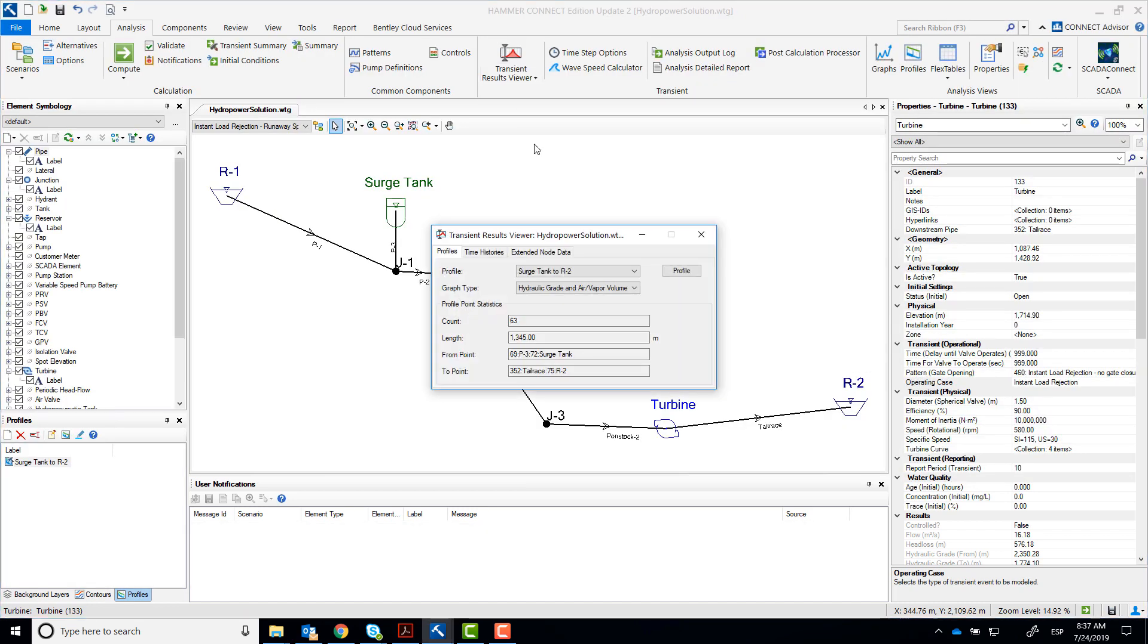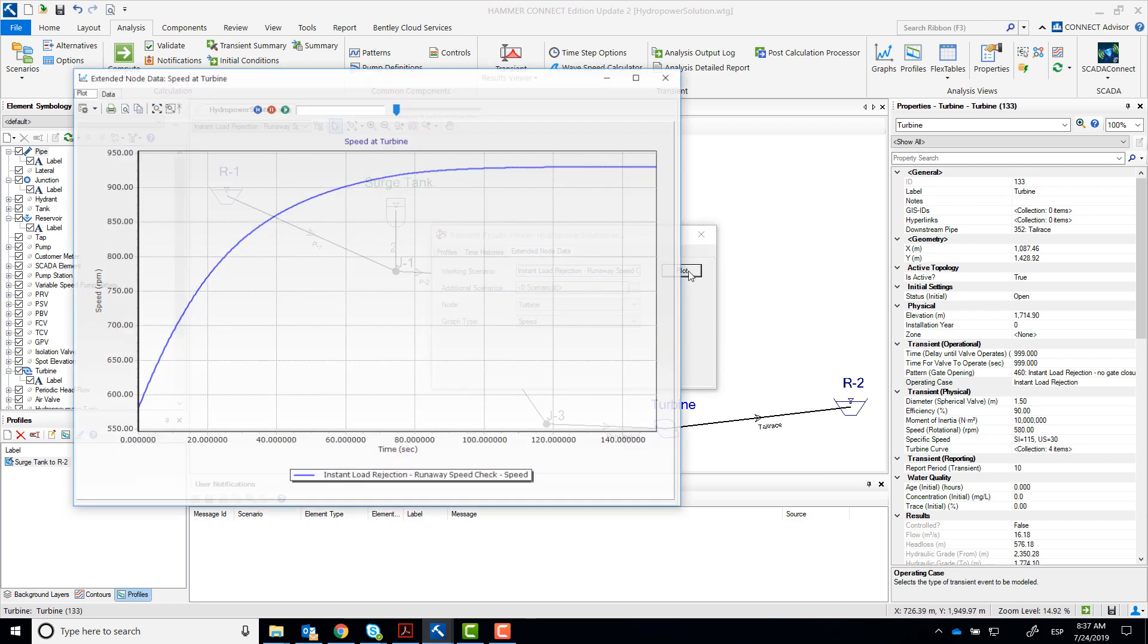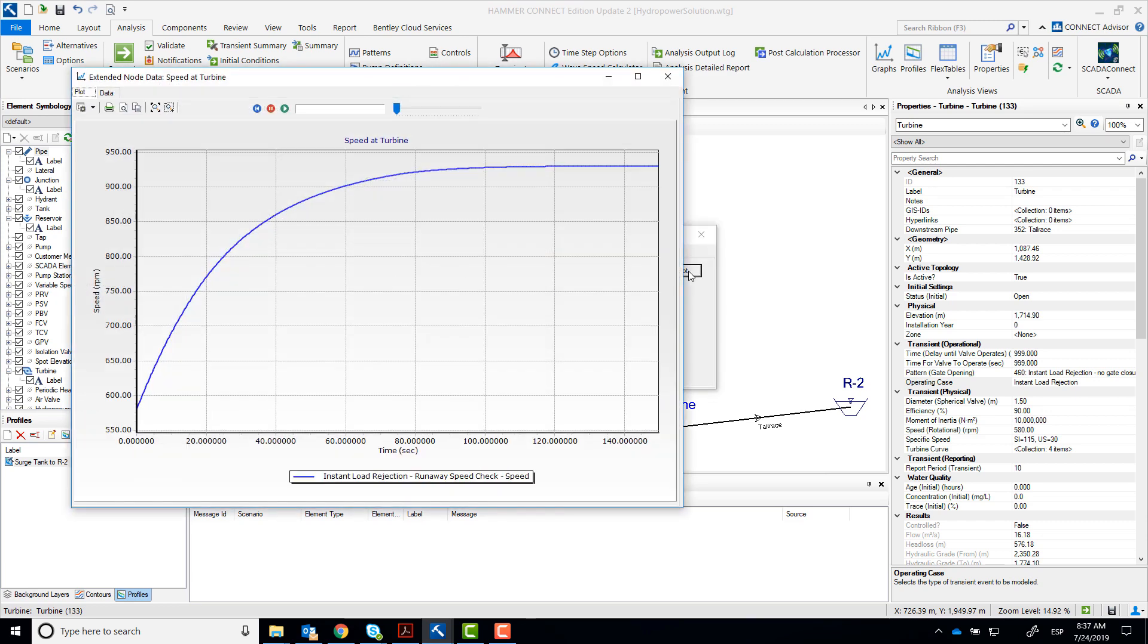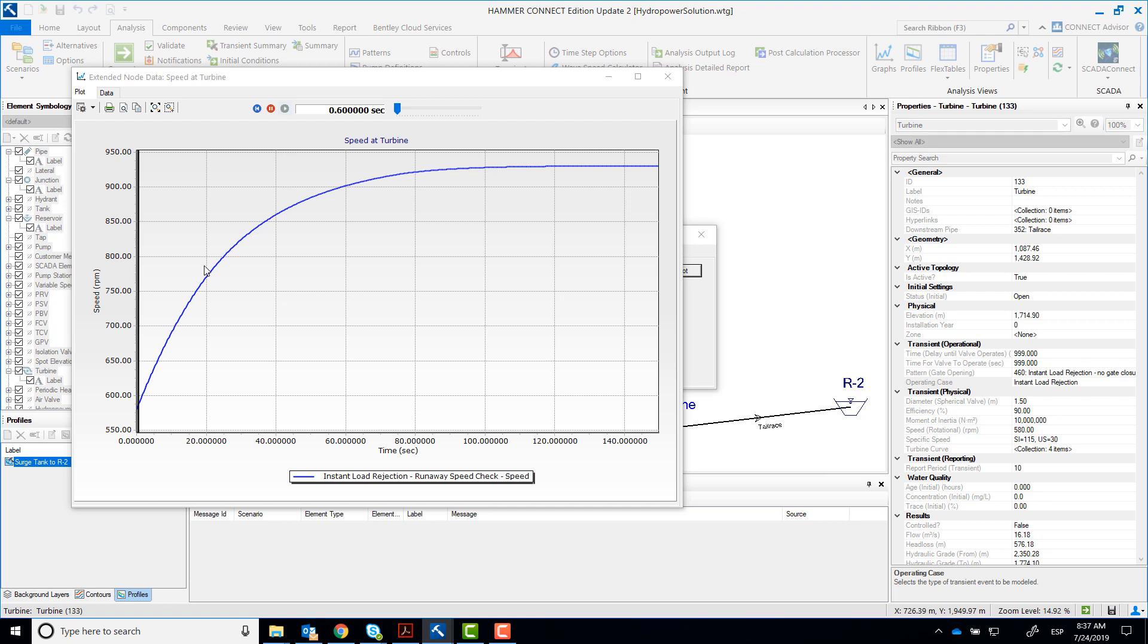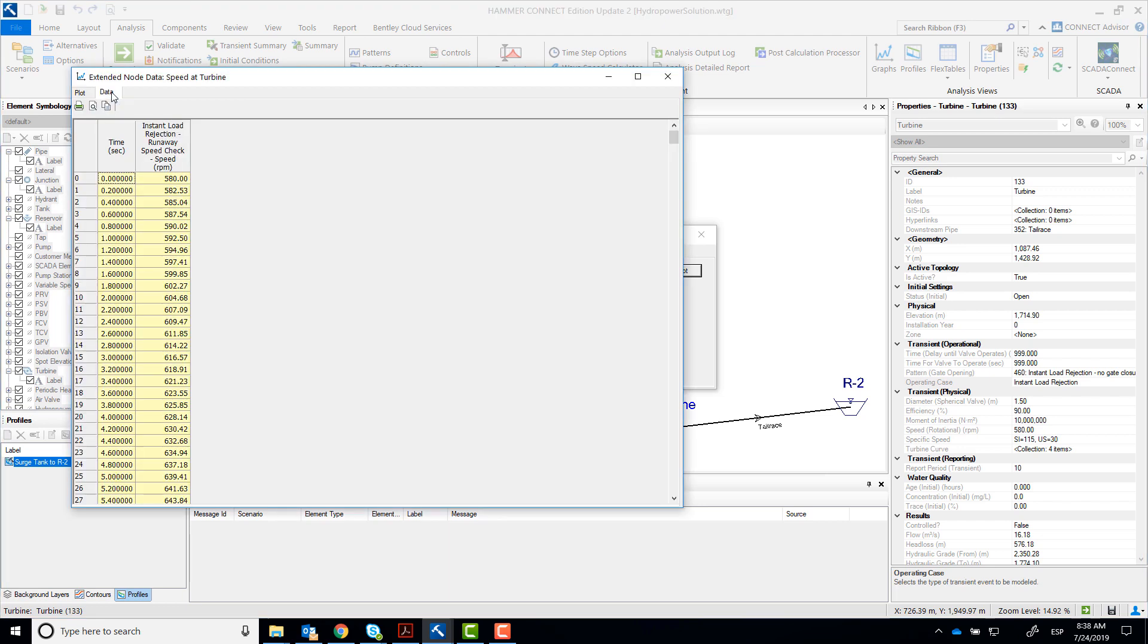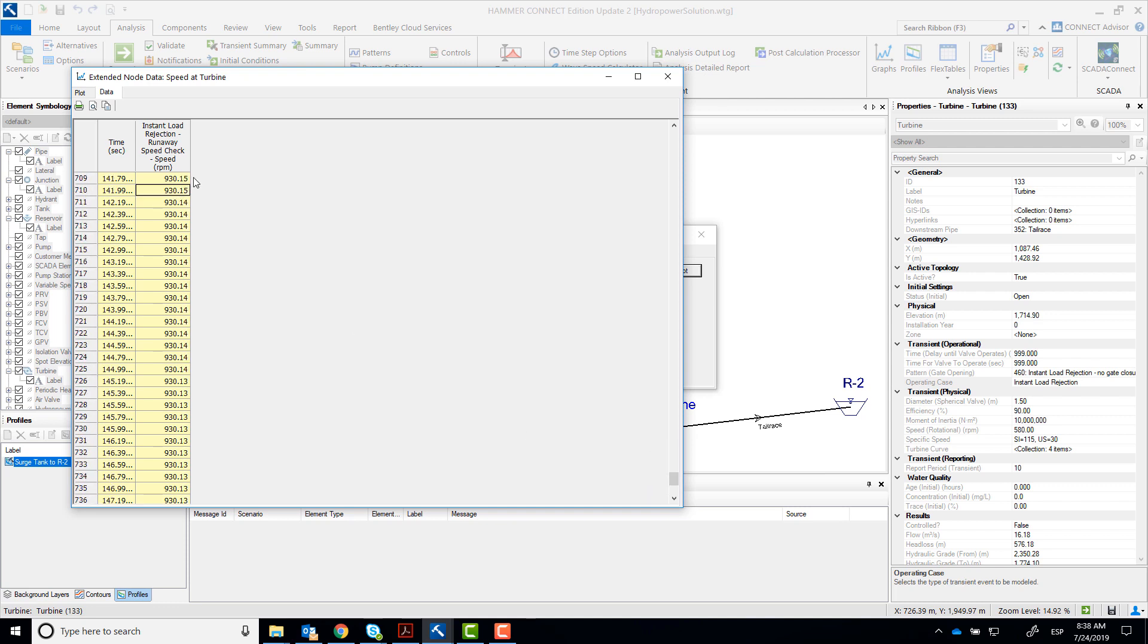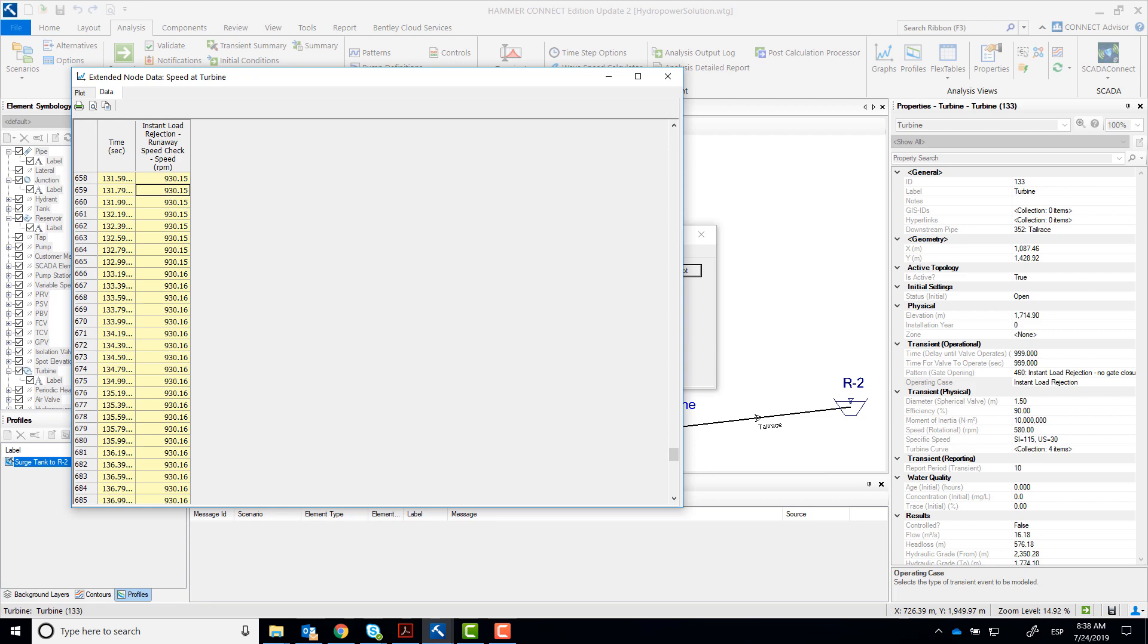Go back to the transient results viewer and select Extended Node Data. We're going to evaluate the turbine's speed. We want to see the maximum speed that was achieved during this simulation. Take a note of the point at which the maximum speed becomes stable. It happens at about 120 seconds and you can see it's 930.1. That's our runaway speed.